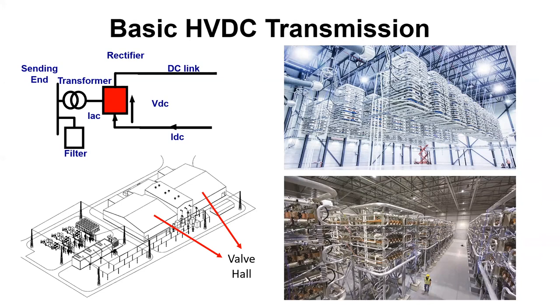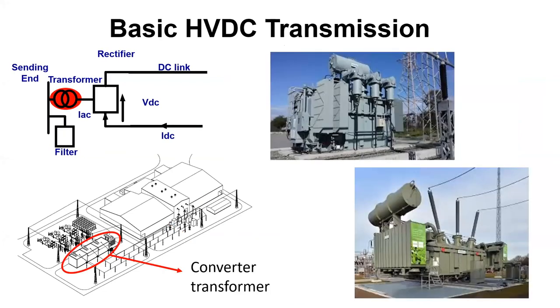Transmission voltage, power rating, type of application, and type of topology play a very vital role in the design of the HVDC system, which must be technically as well as economically feasible. So treat this information as very high level or introductory. Moving on, the next primary equipment within a converter station is the transformer. The top picture shows a transformer with a GIS termination, whereas the bottom picture shows one with air termination. You can see how the dielectric strength of the insulating medium can have a significant impact on the size of the equipment.